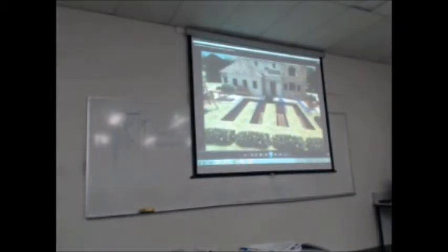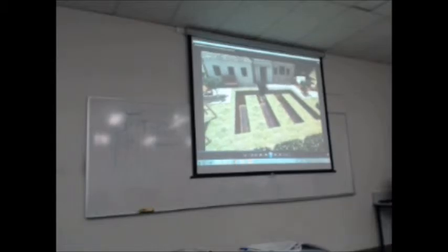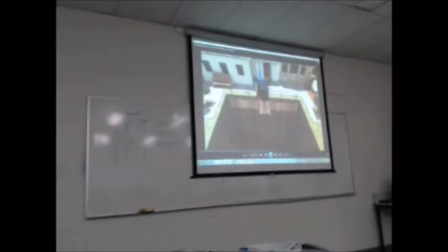A slinky loop is used when land space is restricted. In this example, we used 100 lineal foot trenches to provide enough length for the system to be energy efficient. A vertical loop is used when the required space for horizontal trenches cannot be achieved. Approximately 6-inch holes are drilled and loops are installed and grouted.